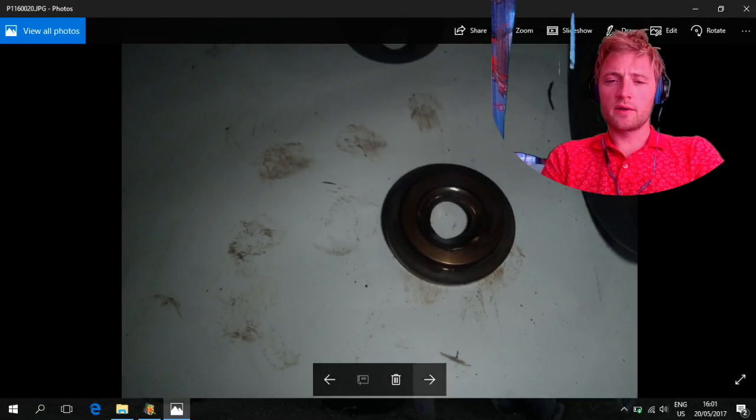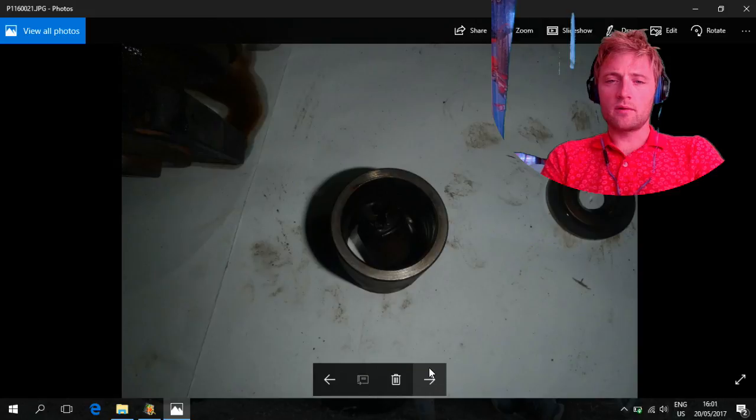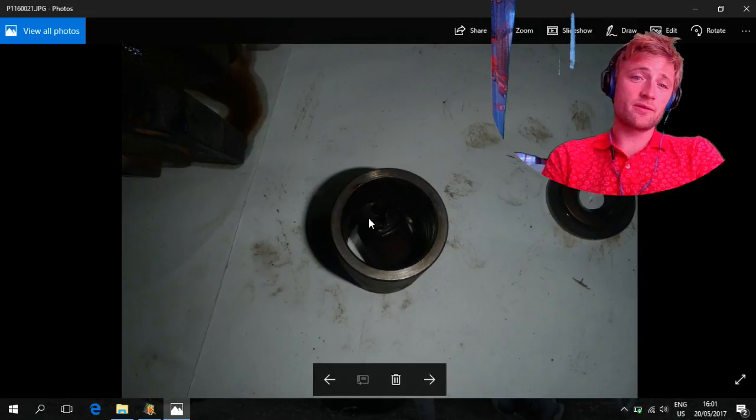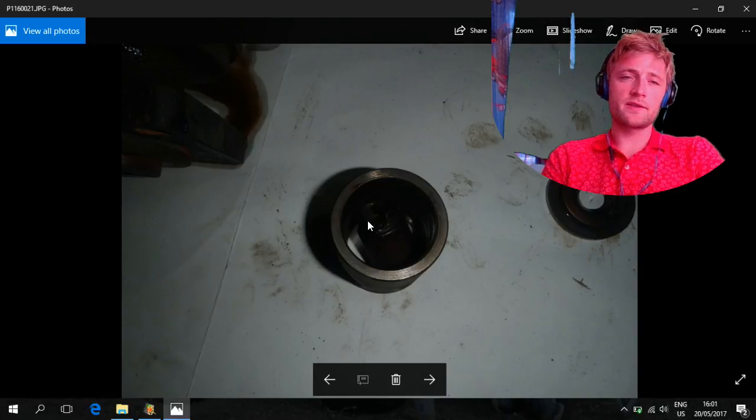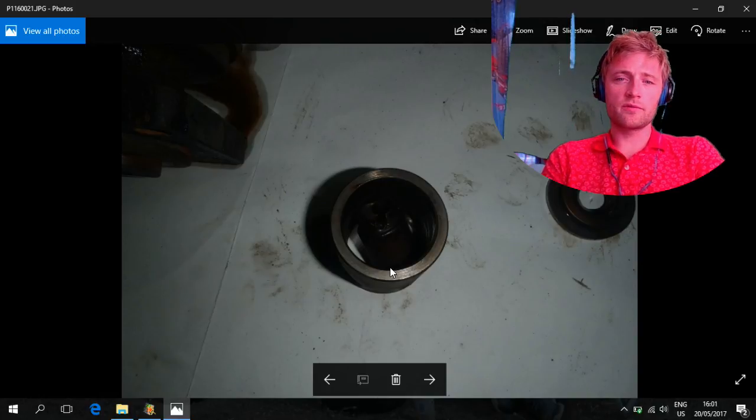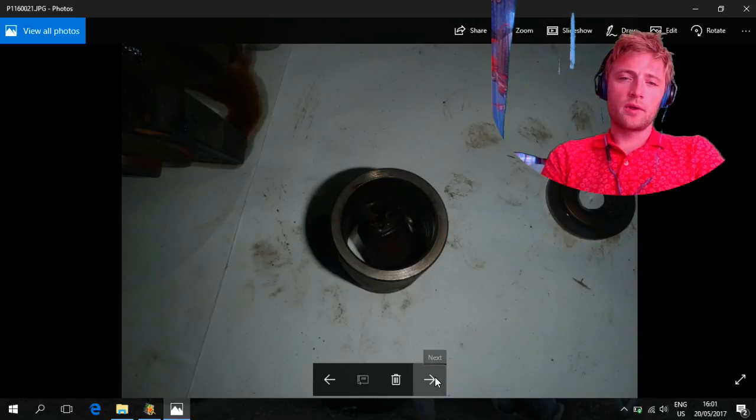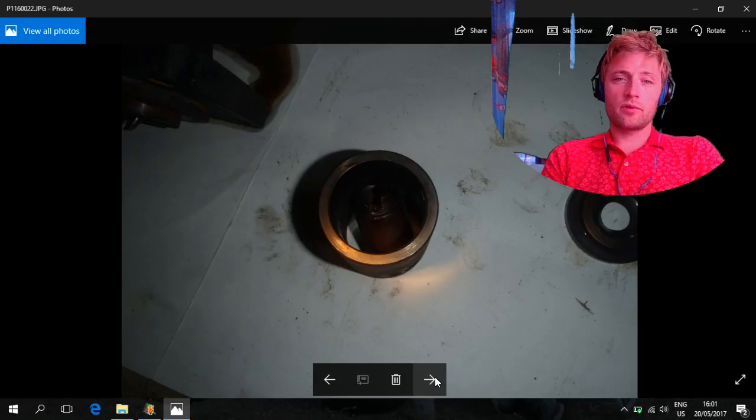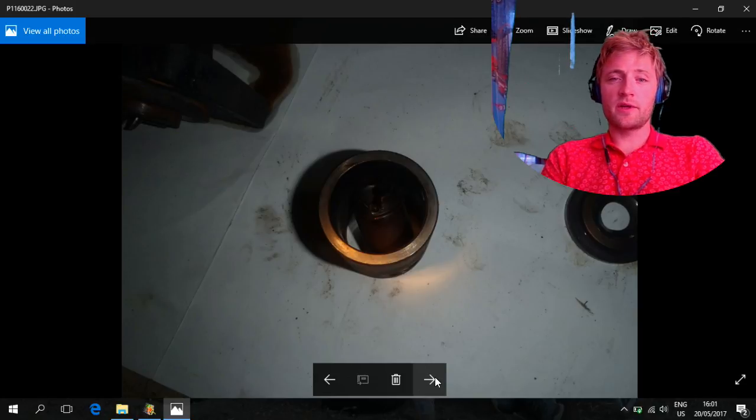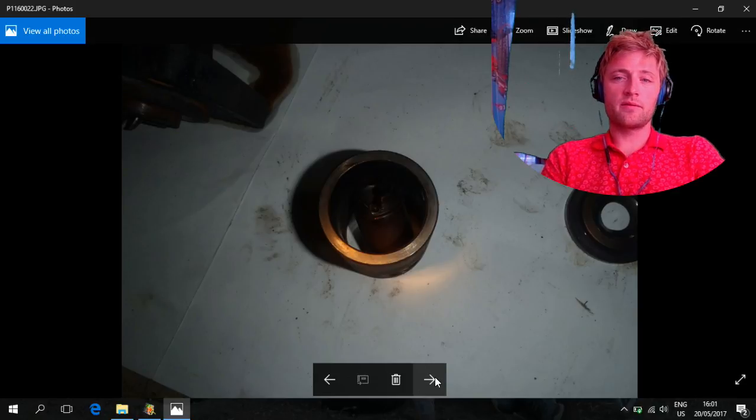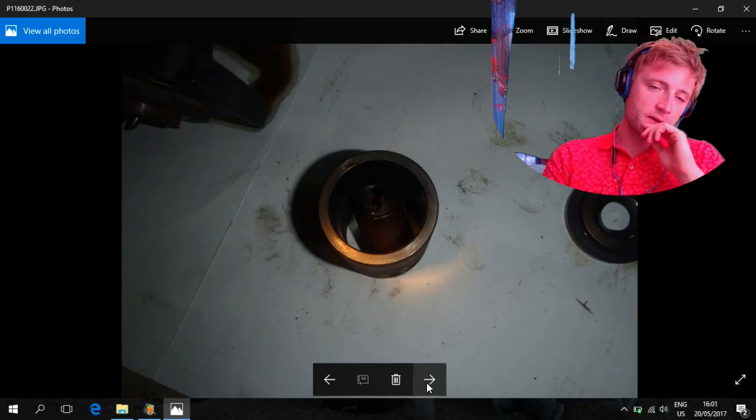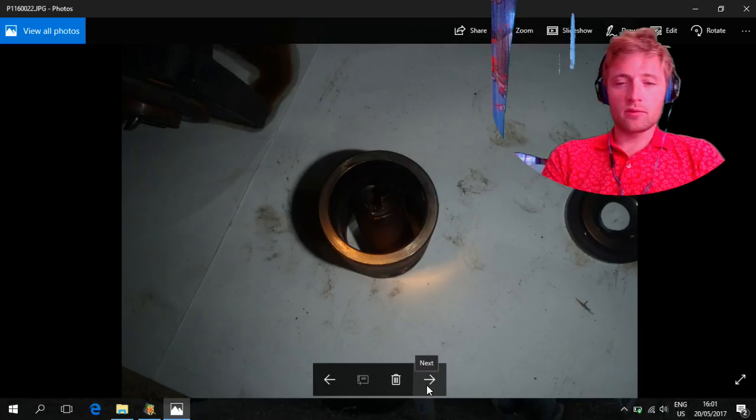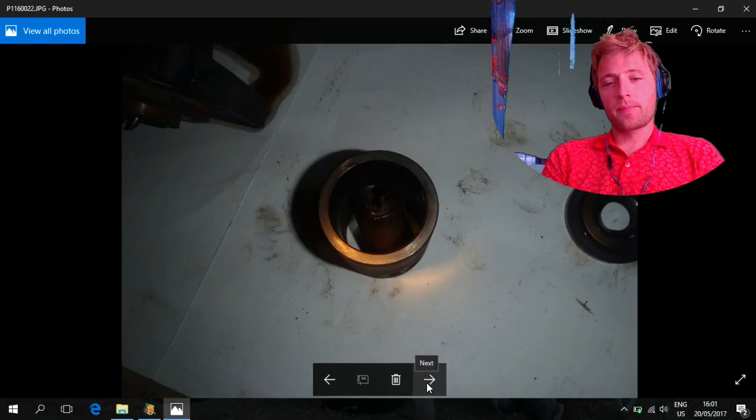As you can see here, the metal is destroyed completely. Also, the piston was broken. That means it was not working; the steam was always full open, and regulation only took place from the inlet valve of the steam.